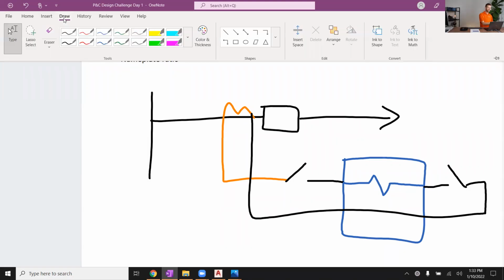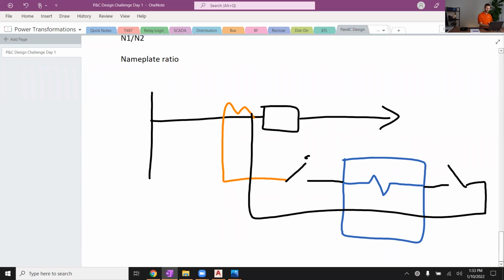And then the key thing that you're looking for is that there's this other shorting block here that kind of goes around and bypasses the current input so that when those test switches are in the open position, it is going around the relay input, leaving it isolated, de-energized, so that there's no current flow through the relay.